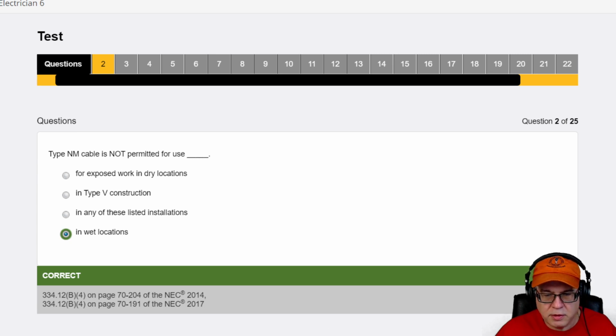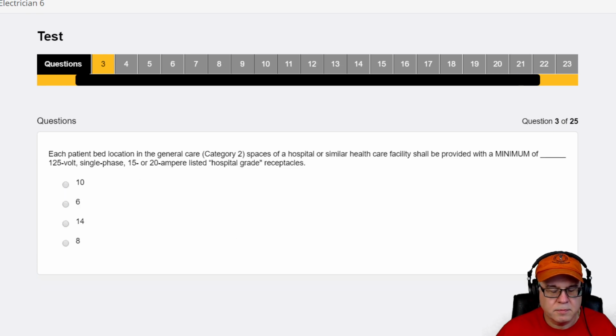All right, let's do another question. I'm just giving it time to scroll. This one says: in each bed location in a general care category 2 space of a hospital or similar healthcare facility shall be provided with a minimum of blank 125 volt single phase 15 or 20 ampere listed hospital grade receptacles.